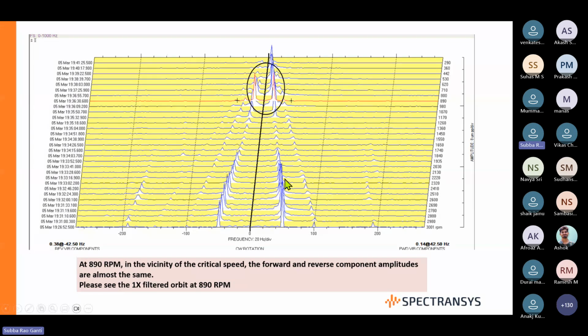This is from another machine. While the machine is coasting down at the critical speed, you can see the forward component and reverse component are almost the same magnitude. This is the point of time when the orbit will look like a fairly straight line or a highly elliptical orbit. As long as the reverse component is smaller than the forward component, the precession will always be forward. Only at any instant when the reverse component is slightly higher than the forward one, at that instant the rotor is likely to exhibit a reverse whirl.